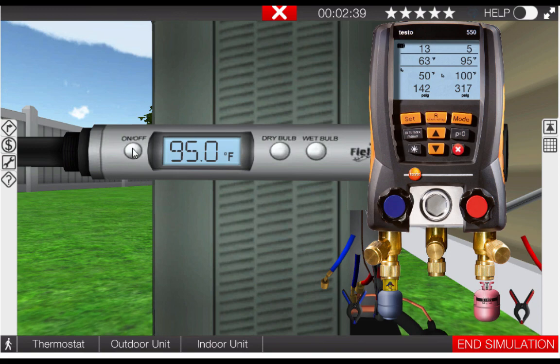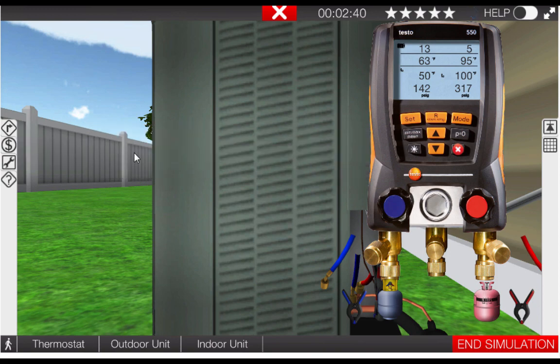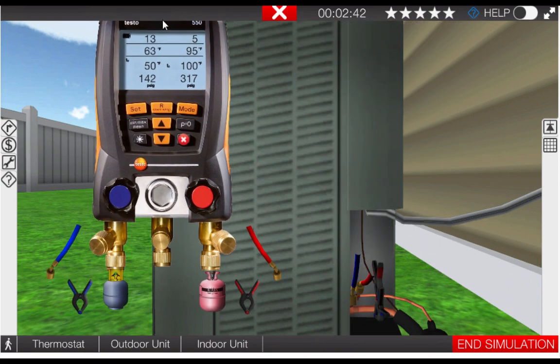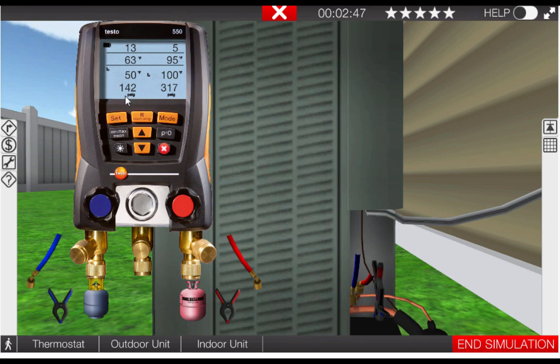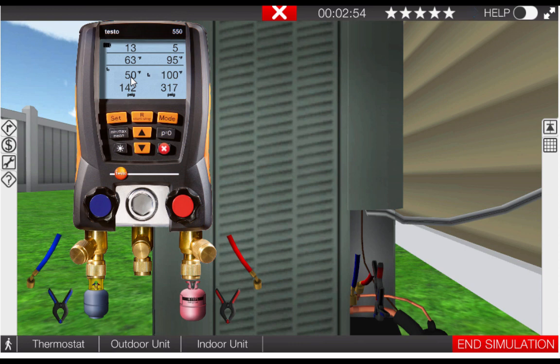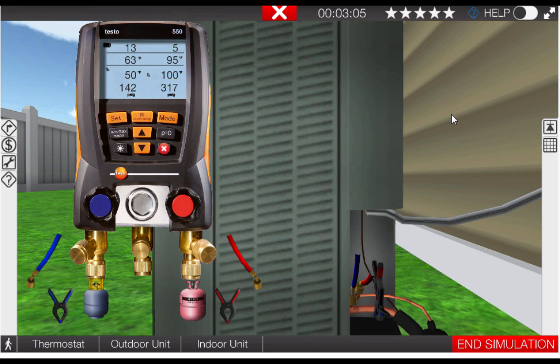Now let's store this psychrometer away and take a look at the suction pressure. Our suction pressure is 142 psig. With R410A refrigerant this results in an evaporating temperature of 50 degrees which is well above where it should be. Normally in the cooling mode air conditioners and heat pumps operate with an evaporating temperature of approximately 35 to 45 degrees although this will largely be dependent on the heat load.